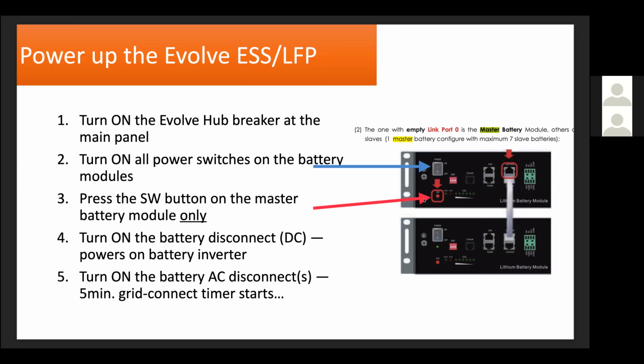first DC cabinet. Once the battery modules each turn on, you'll see the LEDs come on on all the battery modules. And if you've got all of your communications cables and power conductors wired correctly, all of the battery modules will turn on by pressing the red SW button on the first battery module. Once that's on, then you turn on the battery DC disconnector, that DC breaker inside the DC cabinet, and that powers on the battery inverter.